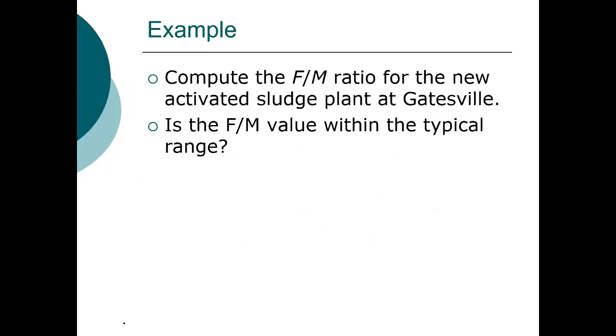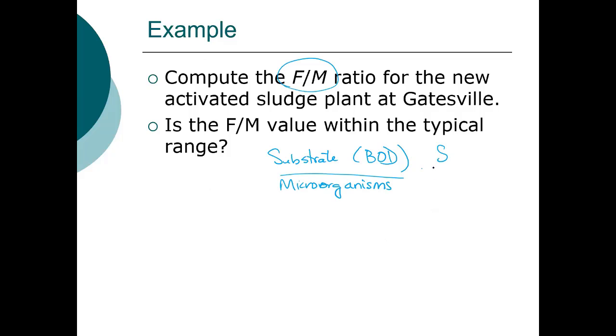Now, the other thing that we use to design these plants is what's referred to as a food to microorganism ratio. And think about this conceptually. So food or substrate, that's the BOD. The soluble BOD is our food. So that's your S. And your microorganisms, that's your X, your mixed liquor volatile suspended solids.